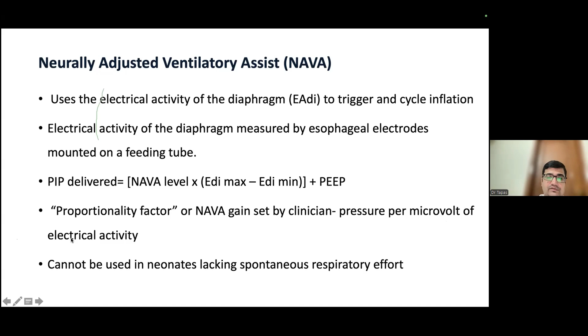And then the machine will deliver the PIP based upon the NAVA level multiplied by this electrical activity of the diaphragm plus PEEP. So what is this NAVA level? This is also known as the proportionality factor or the NAVA gain. This is set by the clinician, and if you multiply this NAVA level with the electrical activity of the diaphragm and combine it with the PEEP, you will get the PIP. So this is how this microprocessor works. The unit of this NAVA level is pressure per microvolt of the electrical activity.